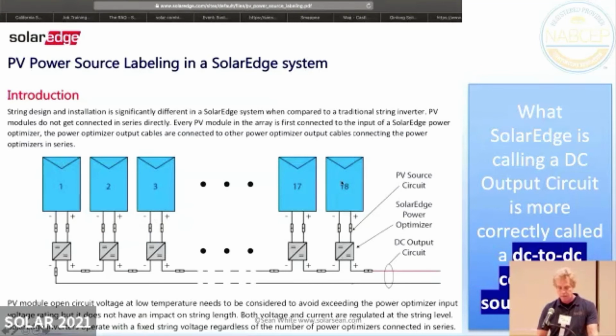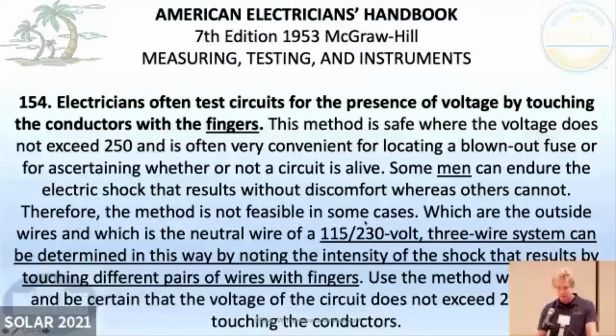So there's a PV module. That's called a PV source circuit before the PV module goes to the DC to DC converter. And then coming out of the DC to DC converter, it's called a DC to DC converter source circuit. So yep, SolarEdge, you got it wrong. They called it a DC output circuit. That is totally wrong. They failed. So just be careful of that.